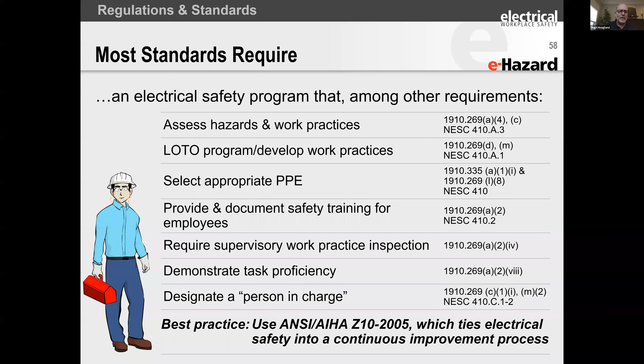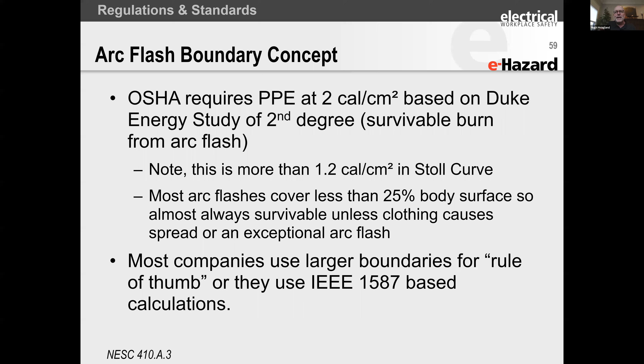The arc flash boundary concept confuses people sometimes. In the US electric utilities, the boundary starts at 2 calories, and in non-utilities, it starts at 1.2. That's the difference between a Duke Energy Power Company study on second-degree burn in arc and the Stoll curve, which was done with flames. It takes a little more energy to burn you in an arc than in a flame, but 70E uses that 1.2 to be a little more conservative.